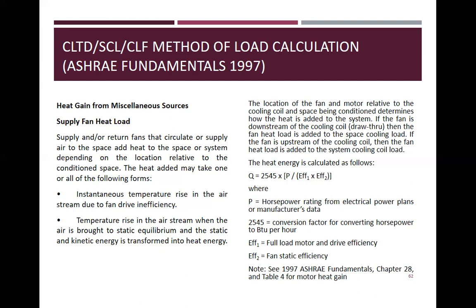The heat energy is calculated as follows. Q is equal to 2545 times P over efficiency 1 times efficiency 2. P is the horsepower rating from electrical power plans or manufacturer's data. 2545 is the conversion factor, BTU per hour per horsepower. Efficiency 1 is the full load motor and drive efficiency. Efficiency 2 is the fan static efficiency. See 1997 ASHRAE Fundamentals, chapter 28, table 4 for motor heat gain.